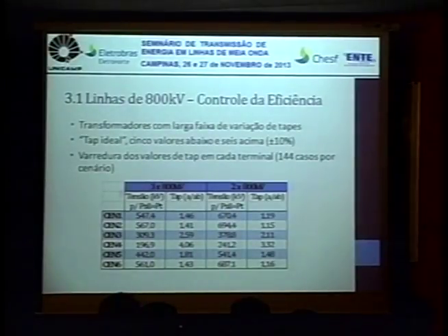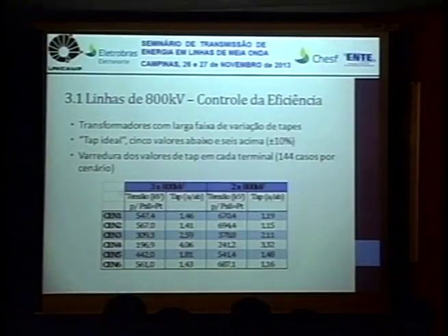And what we're going to do is scan. We fix the tap and then vary the 12 positions in the output. Then we vary the tap in the input, and it varies on the output. So for each scenario, we're always going to calculate 144 cases, and then we're going to try to assess the efficiency and the losses in the line for all these scenarios.